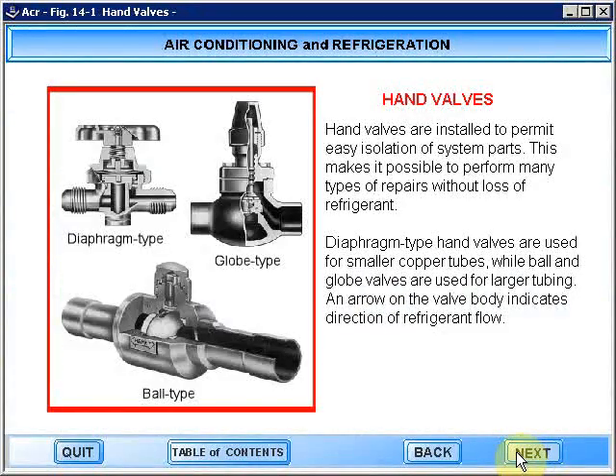Hand valves are installed to permit easy isolation of system parts. This makes it possible to perform many types of repairs without loss of refrigerant. Diaphragm-type hand valves are used for smaller copper tubes, while ball and globe valves are used for larger tubing. An arrow on the valve body indicates the direction of refrigerant flow.